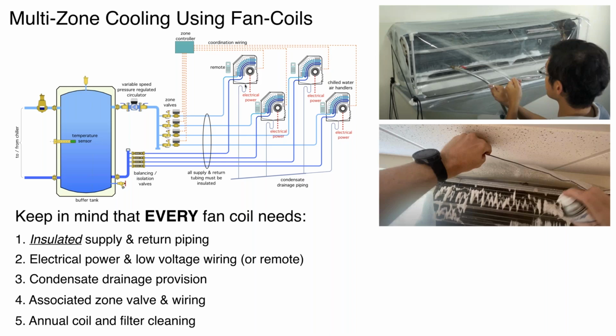They're going to have some deposits on the coil. And there are some companies, there's actually one called WeCleanHeatPumps.com if you want to check them out. And what they do is they put a clear plastic bag onto this unit, and basically it's a catch basin. They have a frame that holds it. And then they use a small electrically powered power washer with some type of a detergent and basically spray down that coil and then allow that material that's been sprayed to drain into this bag.